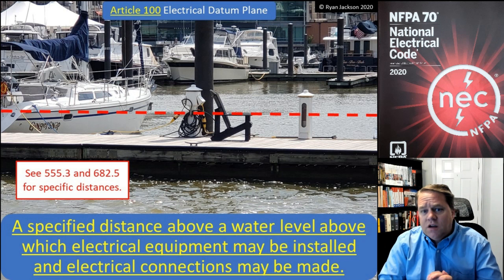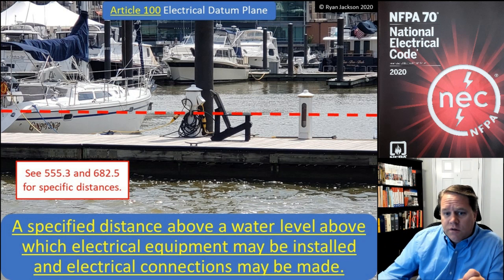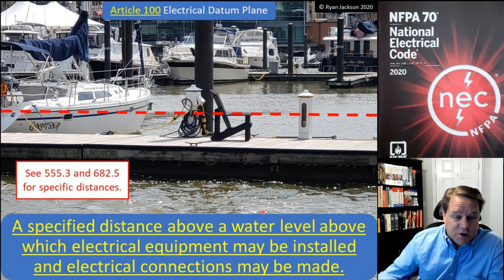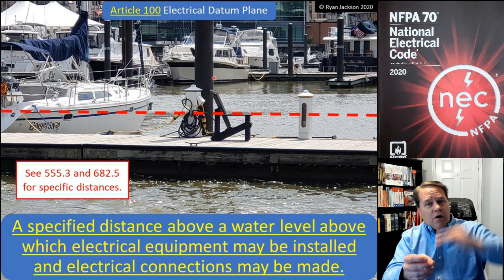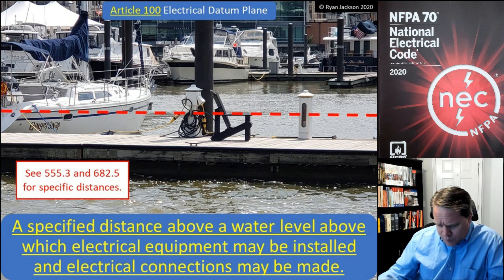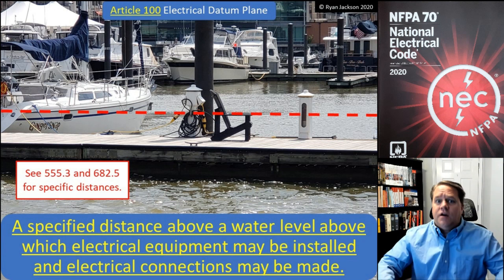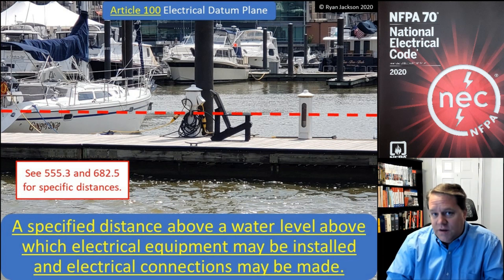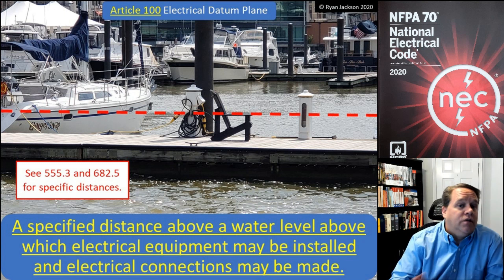Another thing that changes the electrical datum plane is the type of pier — is this a fixed pier or a floating pier? In the picture here, this appears to be a floating pier. The pier is attached to columns, but the columns allow it to go up and down. The electrical datum plane is essentially a line where we say above this you can install equipment and make terminations.